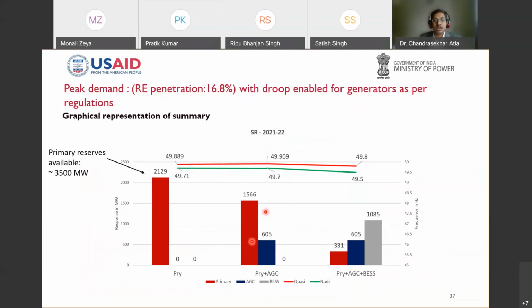Here, this is the concluding slide from the technical studies. So you can see here, don't apply anything. And if you deploy all the reserves, because at present we are given conditions like more than 250 megawatt thermal and 25 megawatt above hydro has to be available for the primary reserve. So in that case, considering the around 60,000 plus installed capacity in the southern region, generations, around 3,500 megawatt, we are keeping as a reserve for the primary reserves. Of course, here it is deploying only 2129, but available in the grid is around 3,500.